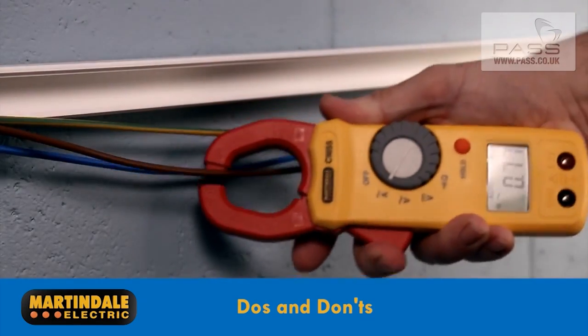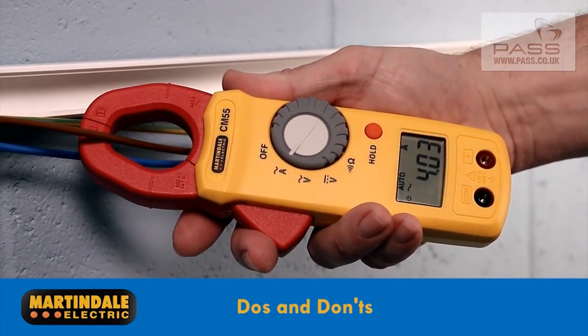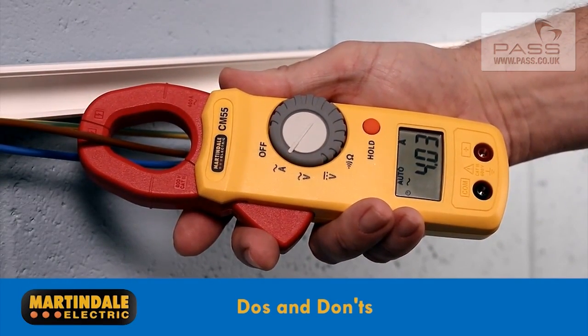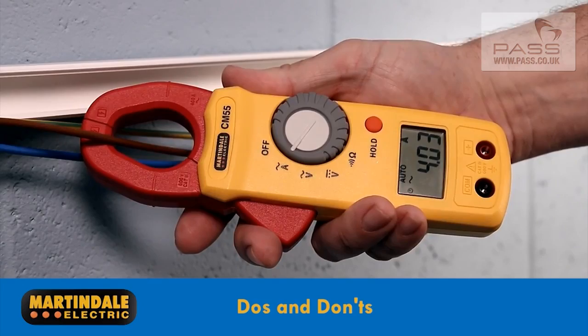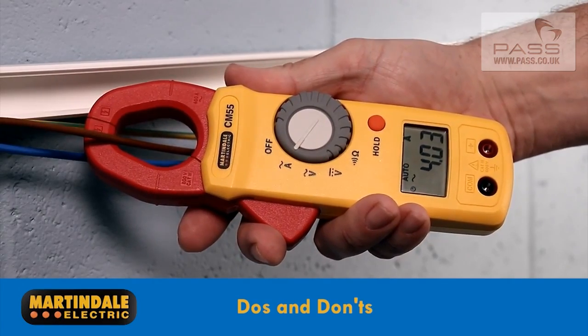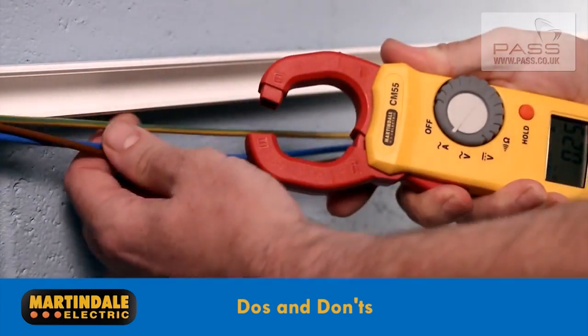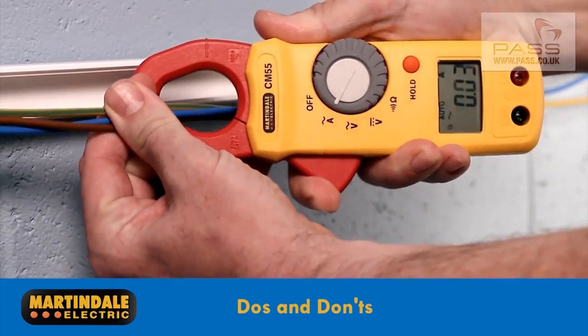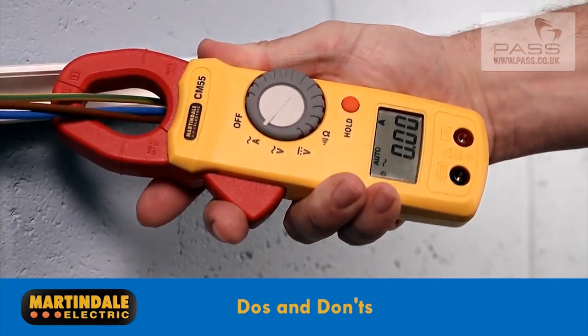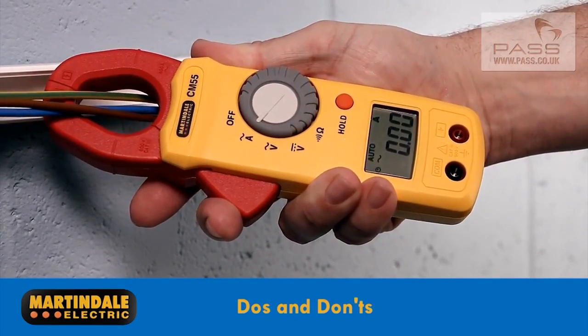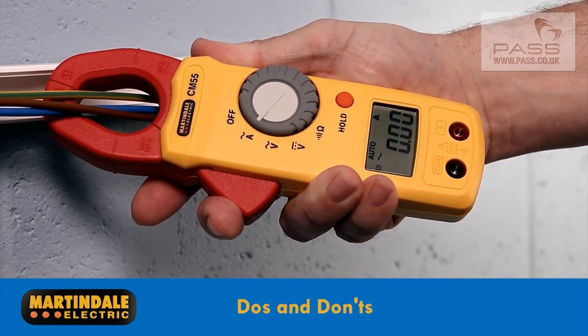When measuring current flow within a conductor, it's important to only clamp around a single conductor, which for multi-core cables may mean splitting out the conductor from the rest of the cable. Clamping around earth, line and neutral in one go will give a zero reading, as the magnetic fields from the conductors cancel each other out.